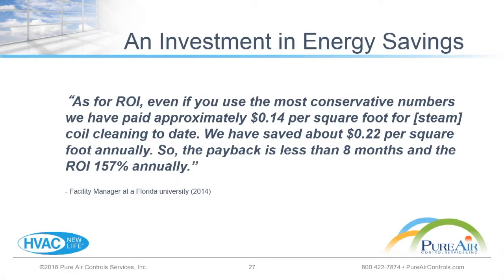This kind of improvement in airflow results in an improvement in operational efficiency. There are obviously a lot of different factors that go into calculating energy efficiency in an HVAC system. But just by way of example, we had a large university where we cleaned about 4 million campus square feet for them a few years back. The cost for them was about 14 cents a square foot to do our proprietary steam process. At the end of the first year, they came back and calculated they were saving about 22 cents per square foot from the steam coil cleaning process. So in their case, the payback was less than a year. You always see significant operational efficiencies from this process. Just another example of the efficacy of using this process as part of our HVAC restoration.